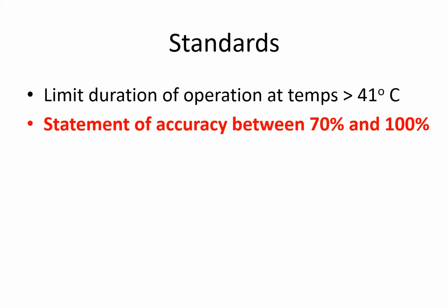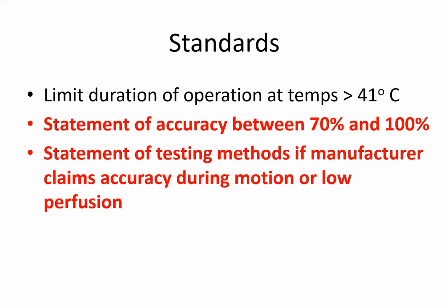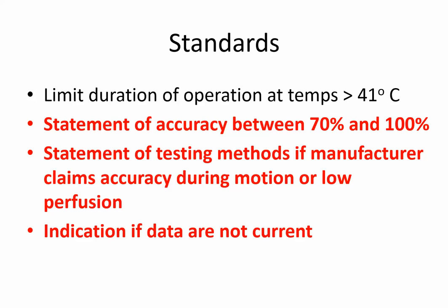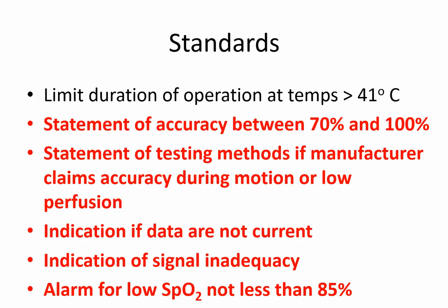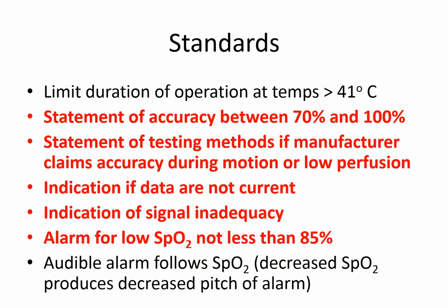There are several standards that manufacturers of pulse oximeters are held to. There's supposed to be a limit of duration of operation at temperatures greater than 41 degrees centigrade. The manufacturer is supposed to state the accuracy of the device between 70% and 100% saturation. If the manufacturer claims accuracy during motion or low perfusion states, there's supposed to be a description of the testing methods used. There's supposed to be an indication if the data are not current, an indication of signal inadequacy, and an alarm for a saturation of less than 85%.